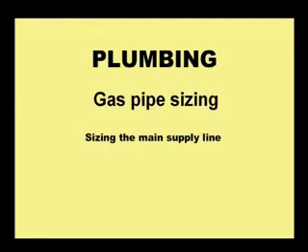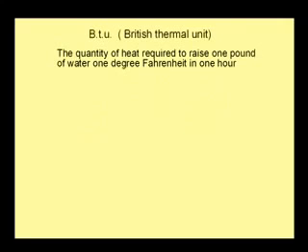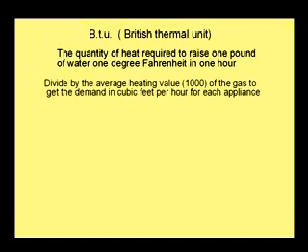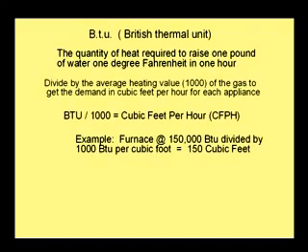This session is designed to give you the basic fundamentals for sizing fuel gas piping used in a residential system. The gas being used has a specific gravity of 0.60 with an average heating value of 1000 BTUs per cubic foot, supplied at a very low pressure, often less than one and one half pounds per square inch. When sizing your particular project, use the BTU rating specified by the manufacturer of the appliance, then divide this number by the average heating value of the gas to obtain the demand in cubic feet per hour required by each appliance. The average heating value of the gas may be obtained from the serving gas supplier.